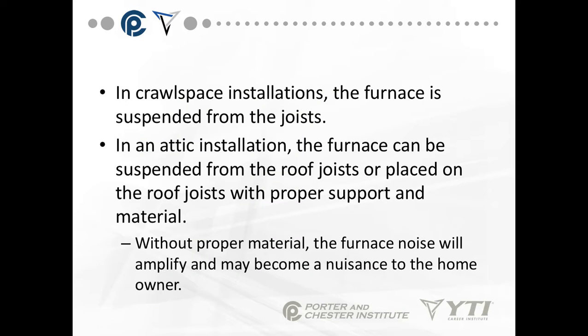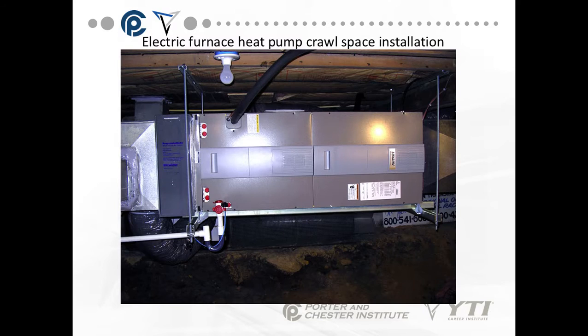In crawl space installations, the furnace is suspended from the joists. In an attic installation, the furnace can be suspended from the roof joists or placed on the roof joists with proper support and material. Without proper material, the furnace noise will amplify and become a nuisance to the homeowner. Little noises amplify really well in overnight hours, okay? A little click when the house is quiet and everyone is trying to sleep sounds like someone banging on the ductwork, so you've got to be very cautious about noise.